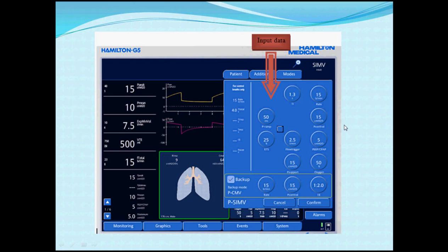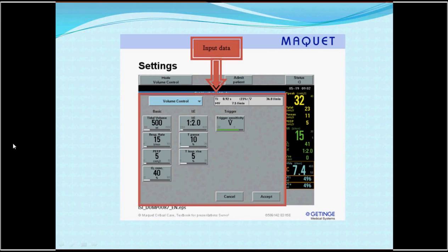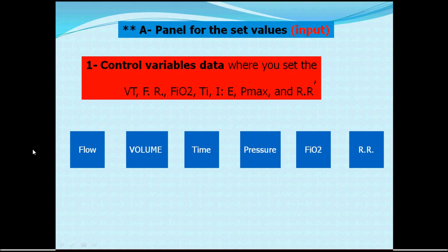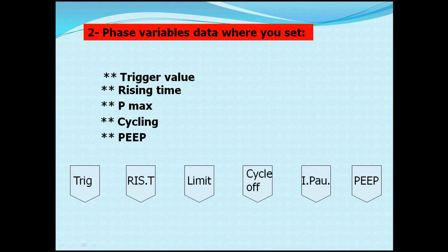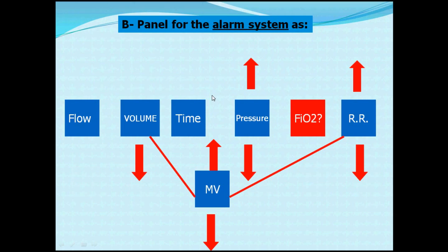Each ventilator has its own way of demonstrating the control panel. For example, the Hamilton ventilator shows the input data and output data separately. When setting control variables, you define flow, volume, time, pressure, FiO2, and respiratory rate according to the patient and mode. For phase variables, you define the trigger type — whether flow or pressure — the rising time, inspiratory limits, and cycle-off criteria. All these must be defined according to the mode of ventilation.